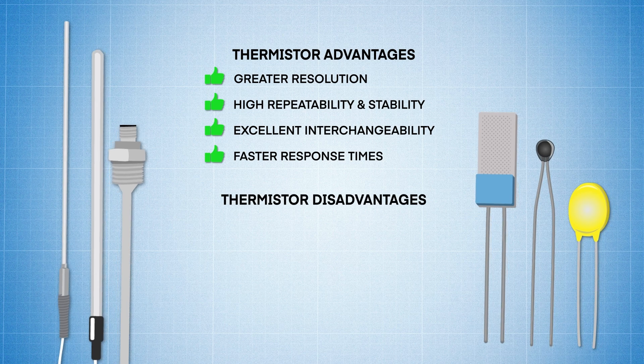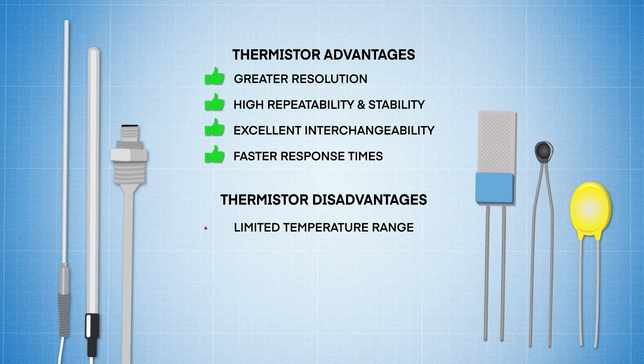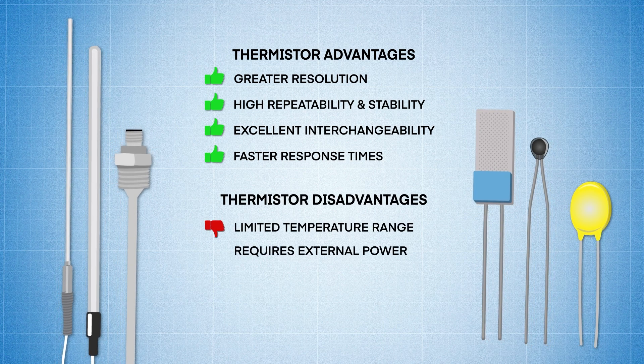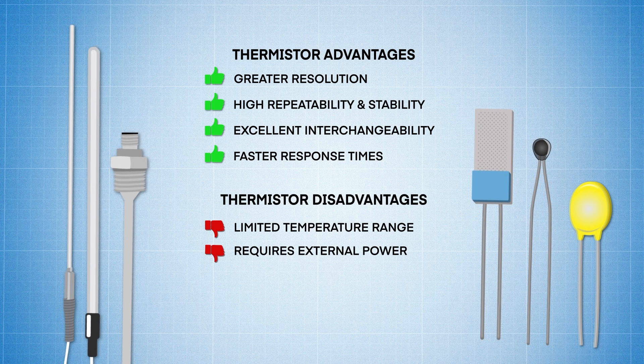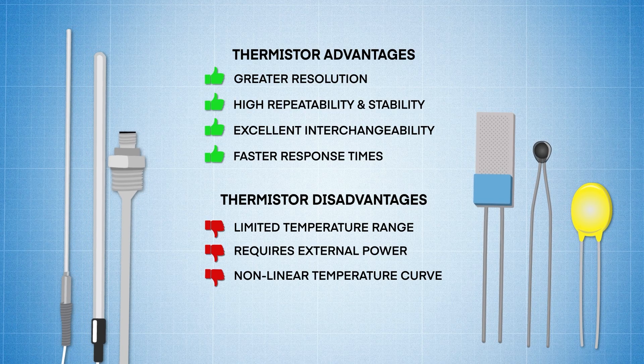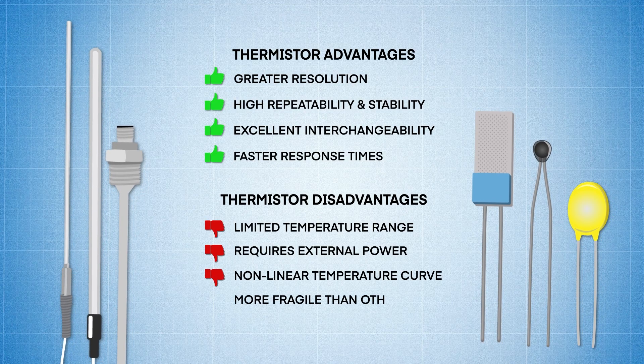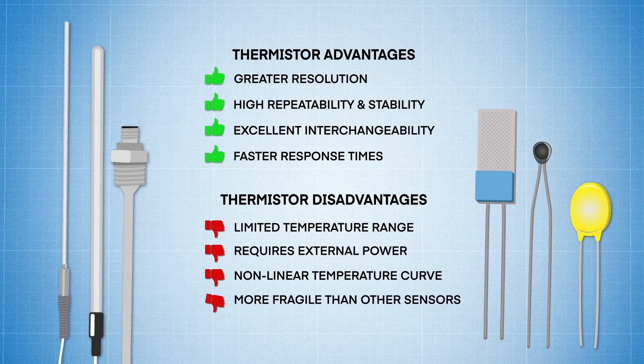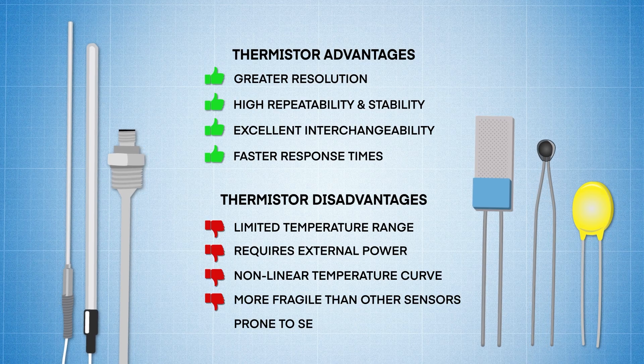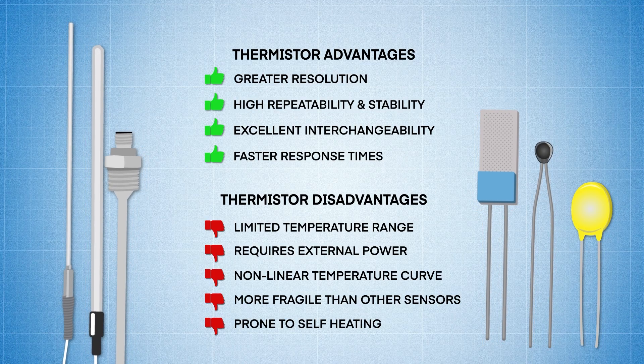However, the disadvantages include having a limited temperature range, requiring an external power source, NTC thermistors exhibit a nonlinear temperature curve, they're more fragile than thermocouples and RTDs, and they're prone to self-heating, which can affect their accuracy.